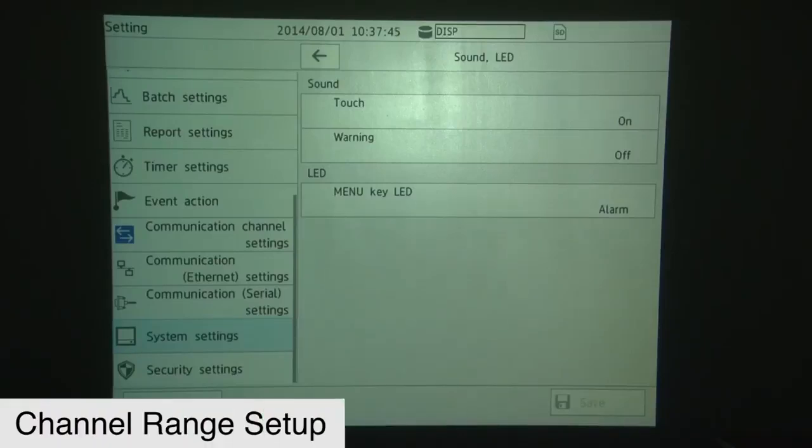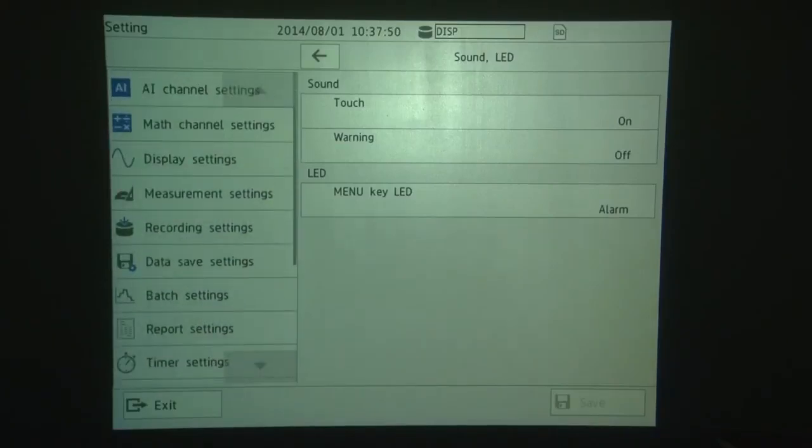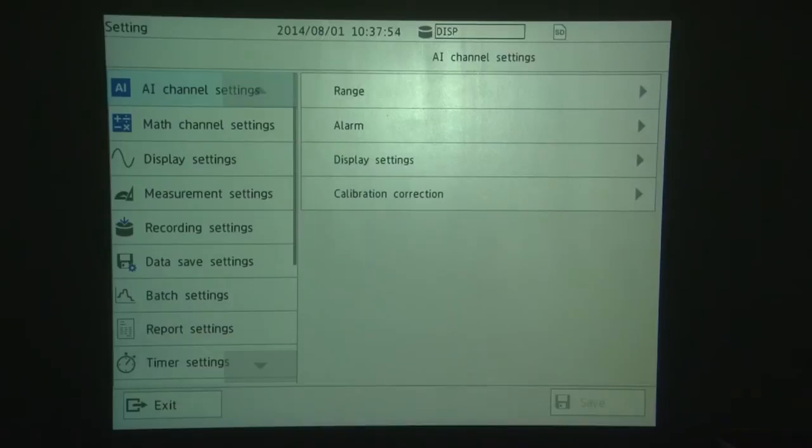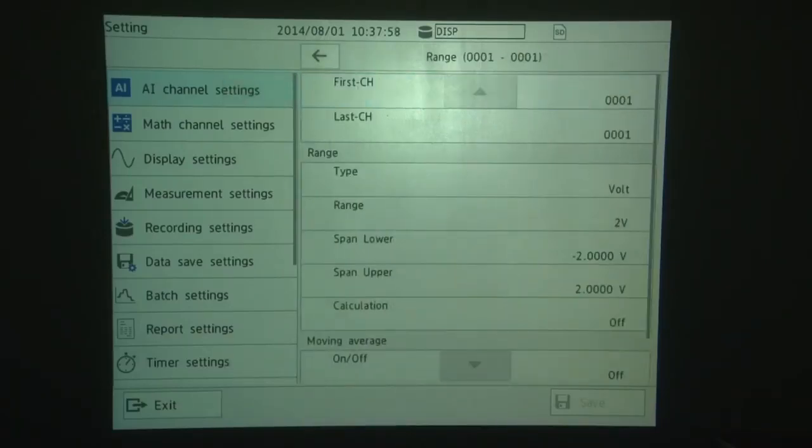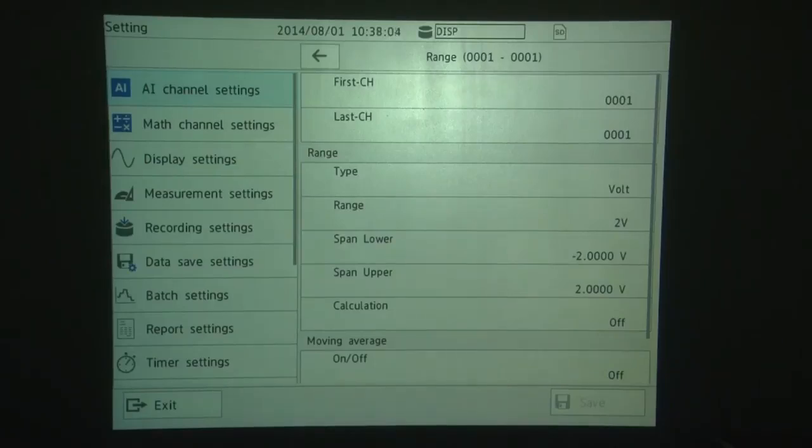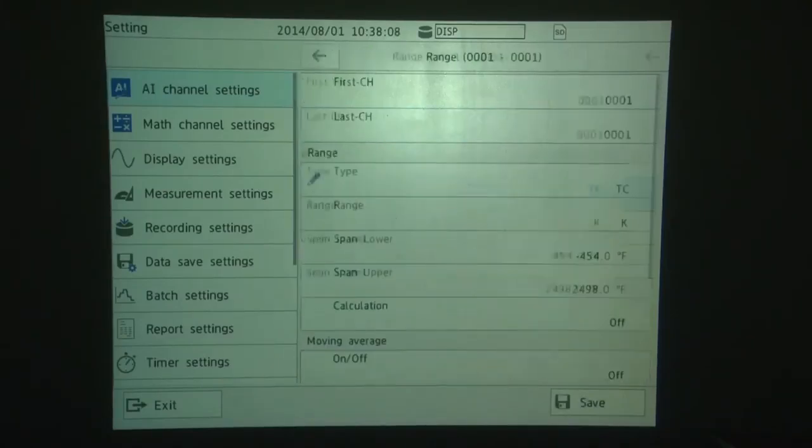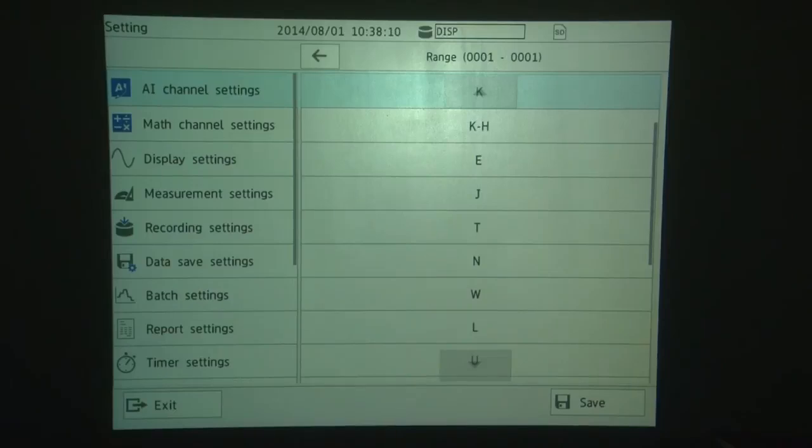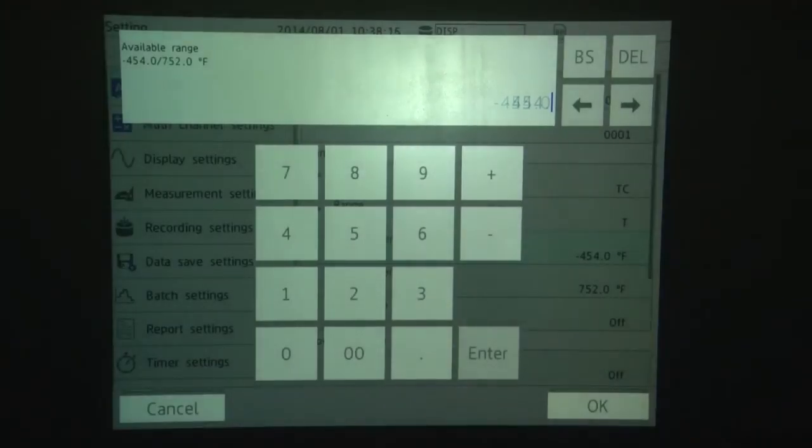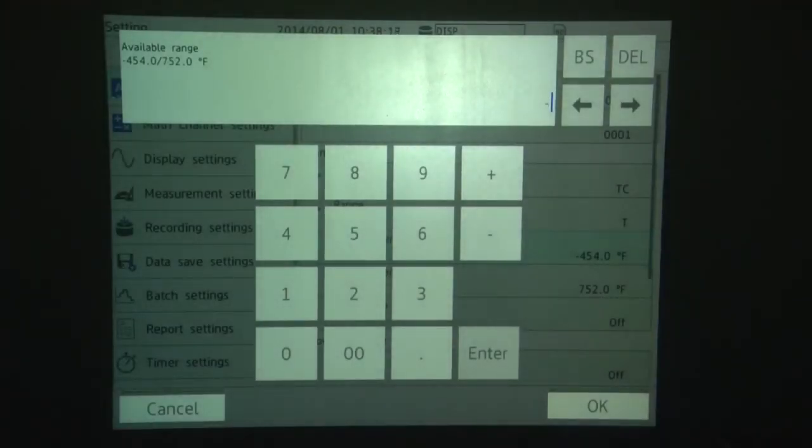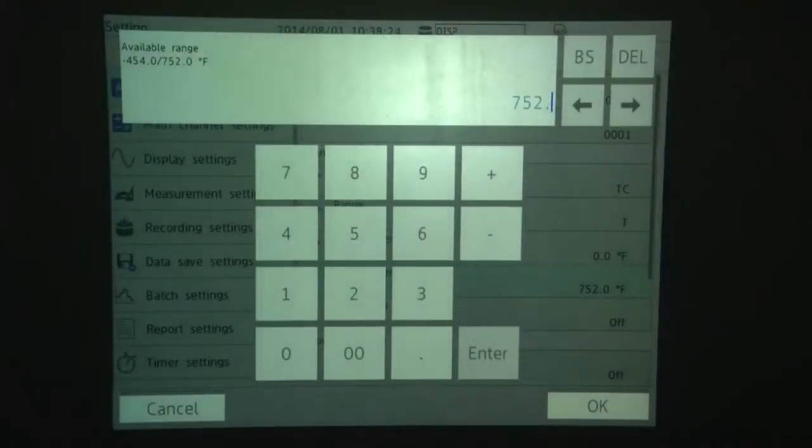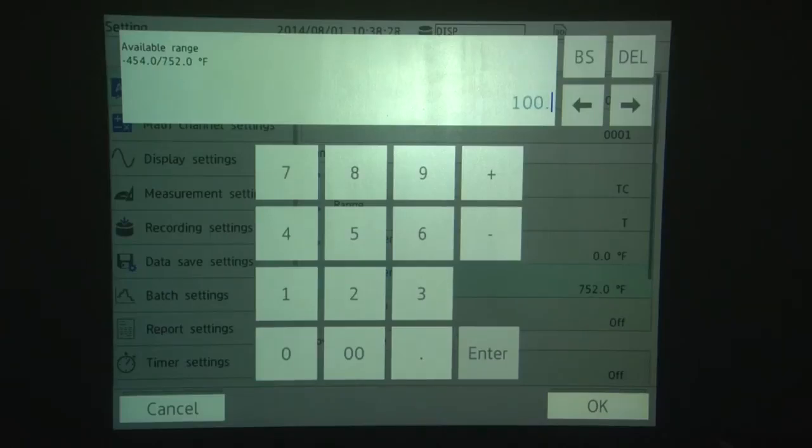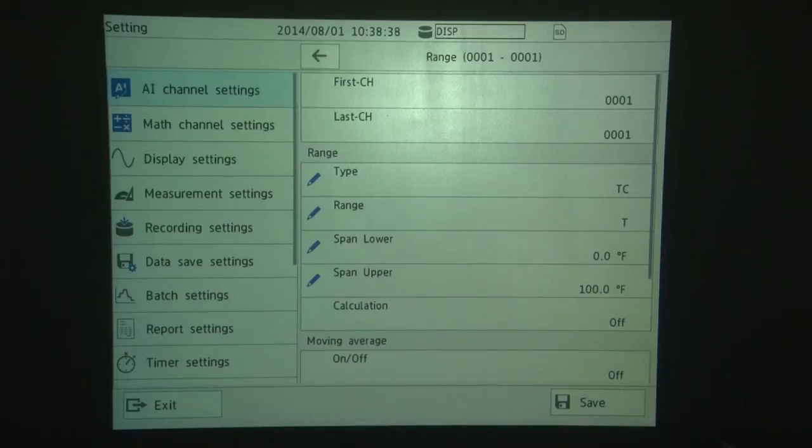We're now ready to set up our channel range. So we're going to touch the menu directory list to the left, bring that all the way back to the top, and we're going to touch AI Channel Settings. We now go to Range. We pick our channel. In this case, we're going to use Channel 001, which is already set as the default. We touch Type. Set that to TC. Touch Range. Set that to T for our T thermocouple. And then we're going to set the Span Lower to 0.0. We're going to set the Span Upper to 100.0. Touch OK. The Span Settings set the upper and lower boundary for the trend scale. Now touch Save when you're done.